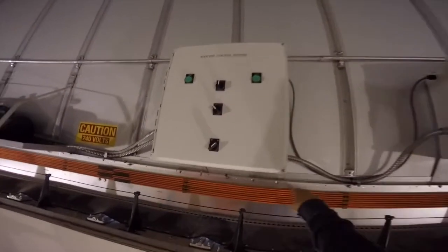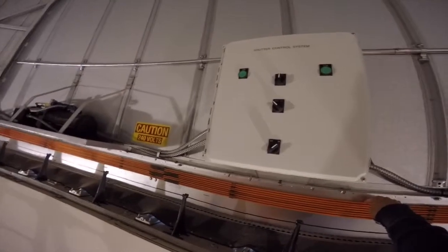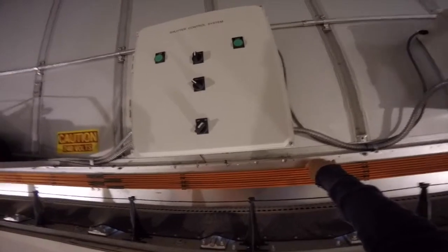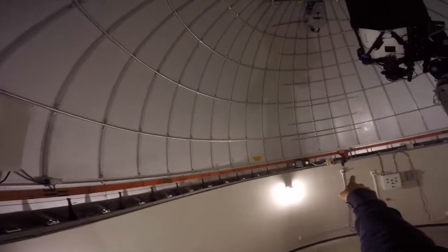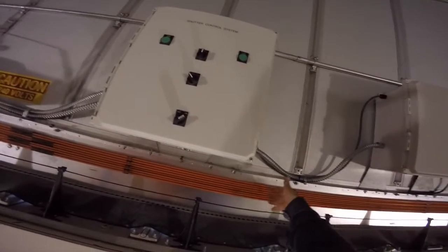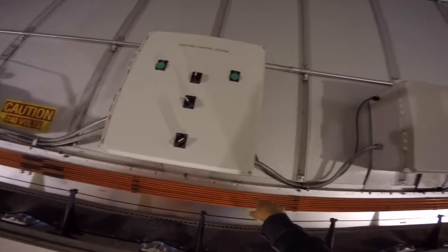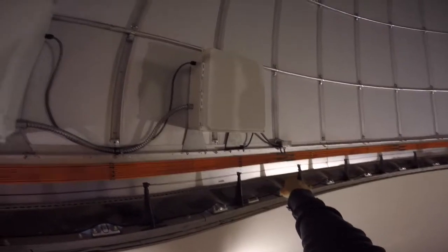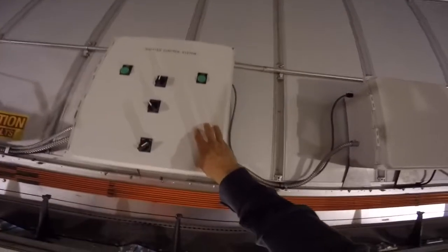These orange slip rings right here transfer power from the base ring that doesn't rotate to a dome that does. Way over on that side, that red sort of piece of metal behind it are actually fingers that rotate in these tracks and send electricity into the tracks. And then right over here, that little box right there pulls electricity out of the tracks, sends it up to the radio control unit, and then over here to the main shutter unit.